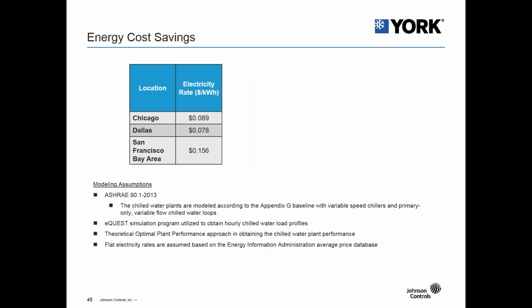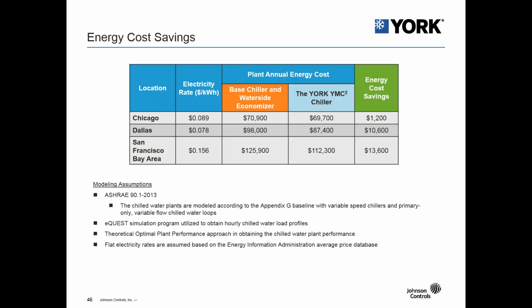So we looked at 3 different locations, Chicago, Dallas, and San Francisco. And the modeling assumptions are shown below. Chillers were selected based upon ASHRAE 90.1, the 2013 requirements. And the chilled water plants are modeled according to the Appendix G baseline with variable speed chillers and primary only variable flow chilled water loops, and it was simulated with eQuest.